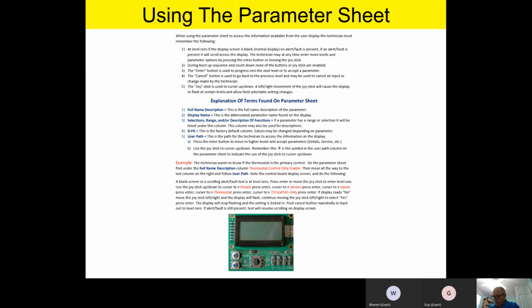So what I'll do is I'll go down to my thermostat only control, and then I need to get into our thermostat only control enable. And so if I go to my parameter sheet and I go to my user display and I poke enter, it's going to take me to the next level. And then I'm going to scroll through until it says details, and I poke enter.